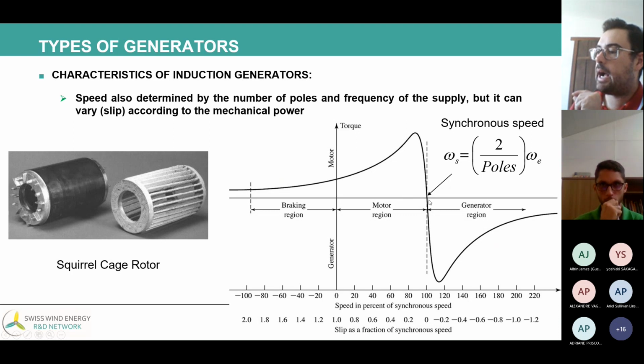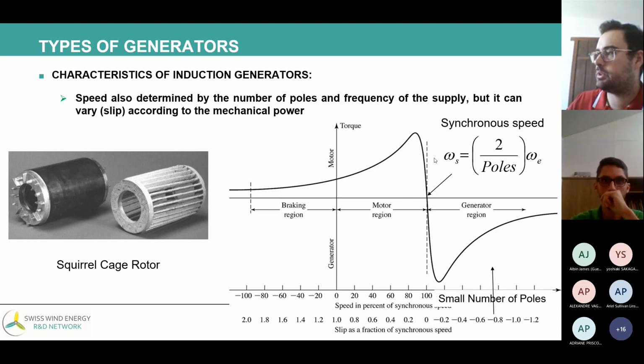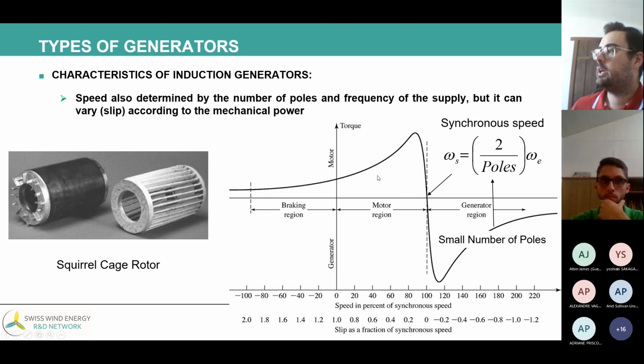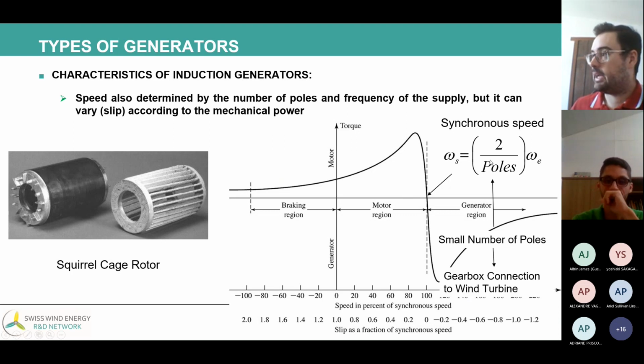And the higher the speed, the higher the electric energy produced by the generator. But the region of operation of this machine is not a wide range. It's a small range of variation of speed, some rotations per minute. Another characteristic of induction machines is that we have 4, maximum 6 poles, as Cesar said. That means that when you use induction generators, we need a gearbox. This is mandatory. When using synchronous, we can have a gearbox or not.